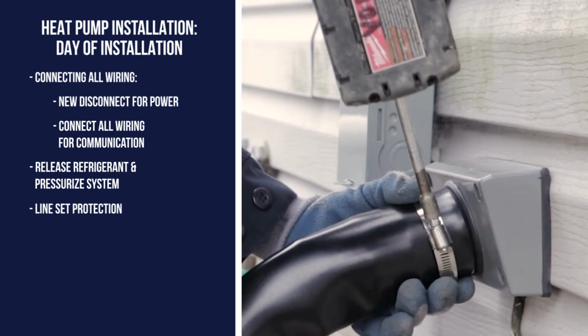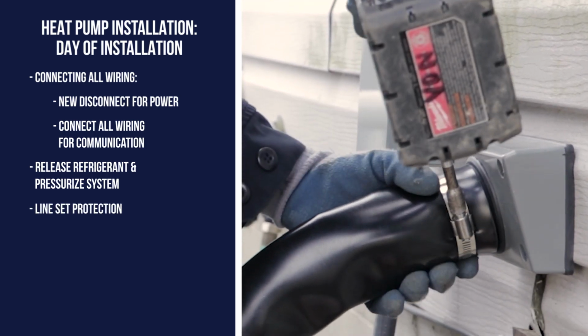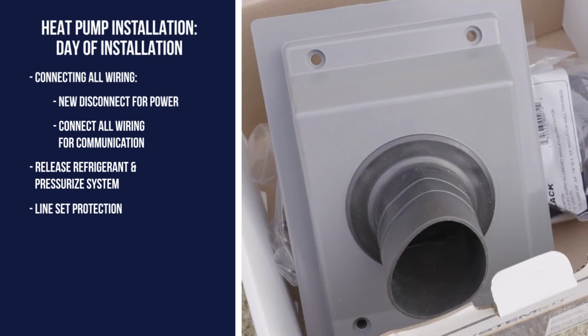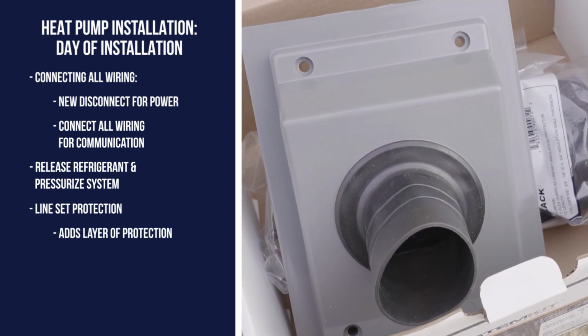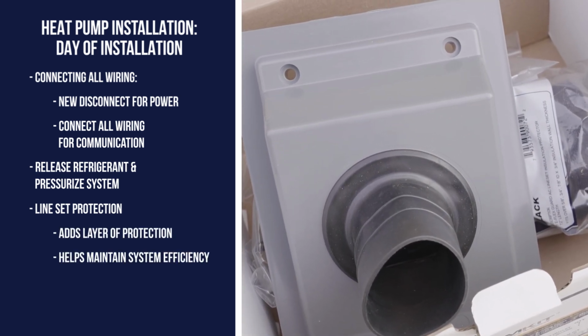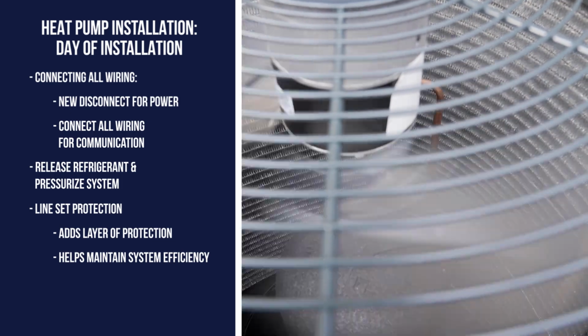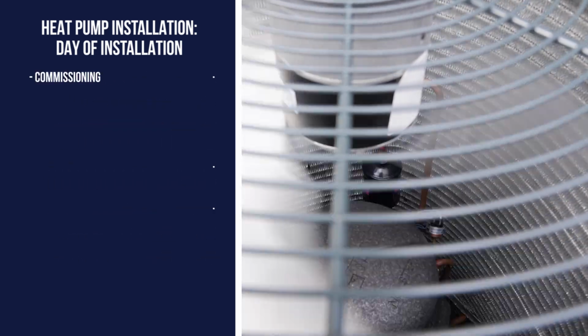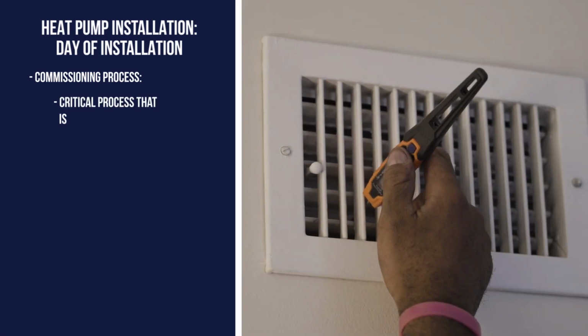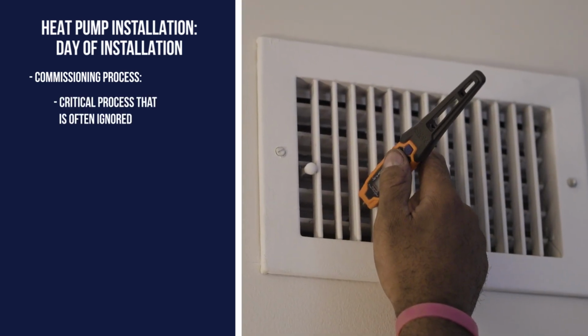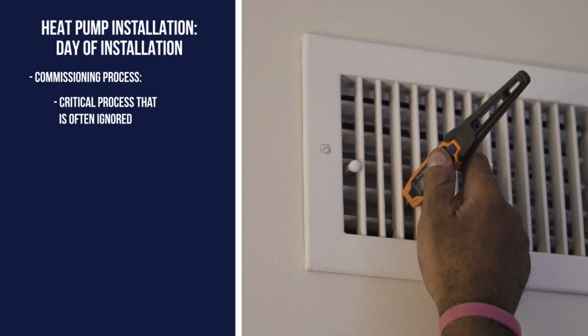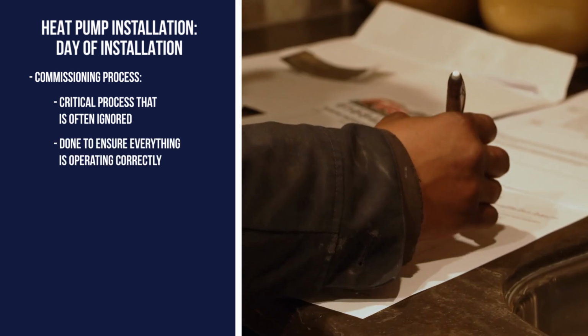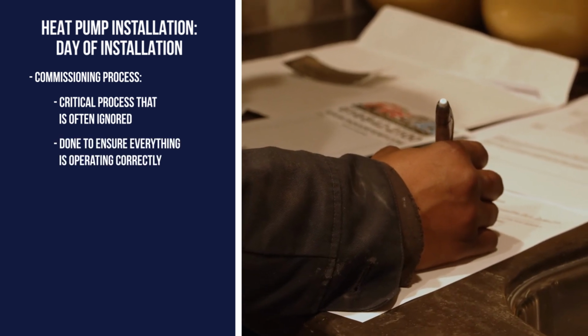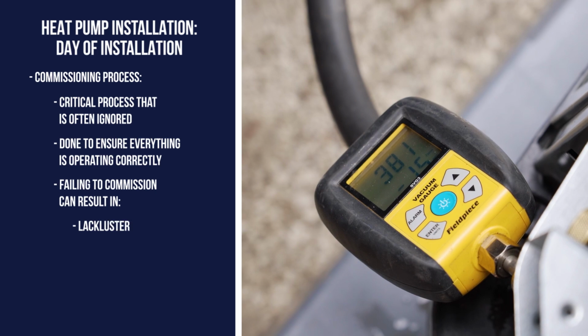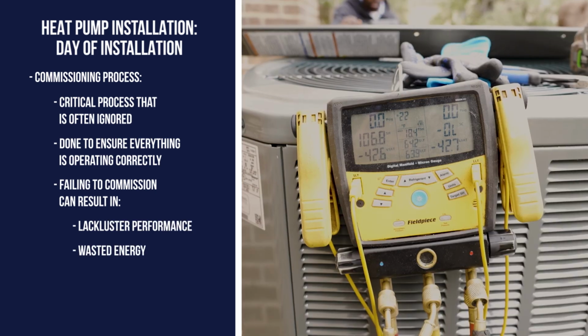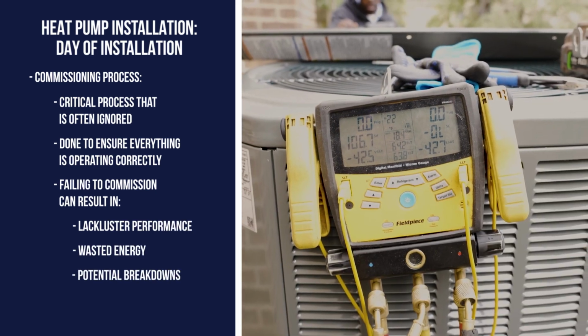During this time, we will add line set protection to each heat pump we install. Line set protection adds a layer of protection from the elements and helps maintain your system's efficiency. Once the system is charged, it's time to turn everything on and commission the system. Commissioning new HVAC equipment is critical and often is ignored by HVAC contractors. It's done to ensure everything is operating as it should. Failing to commission a heat pump can result in lackluster performance, wasted energy, and potential breakdowns.